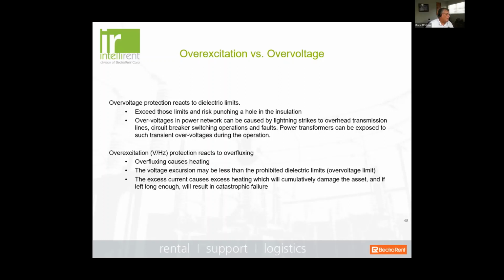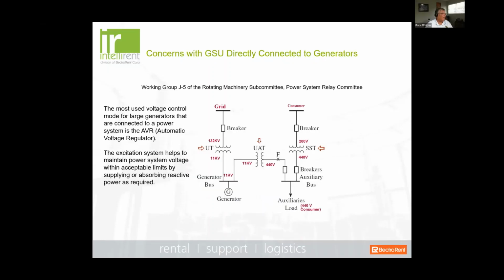Well, what is overexcitation? Well, we also refer to that as overfluxing. And that's the voltage excursion that may be less than prohibited in terms of dielectric limits. So in other words, if you're just talking about voltage, the overvoltage condition would be high, but down at this level, which is still high, but your frequency is dropping, now you've got a cumulative problem that can cause excessive heating and damage to the asset.